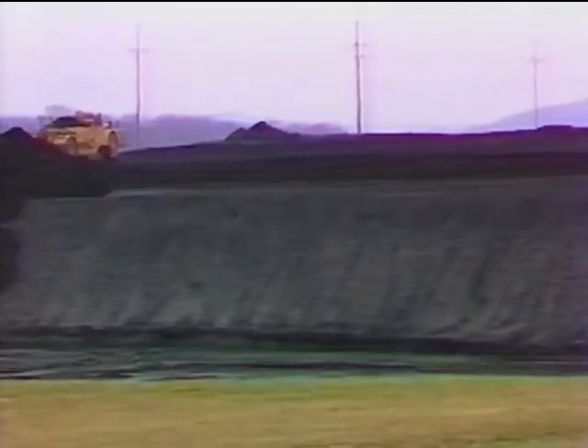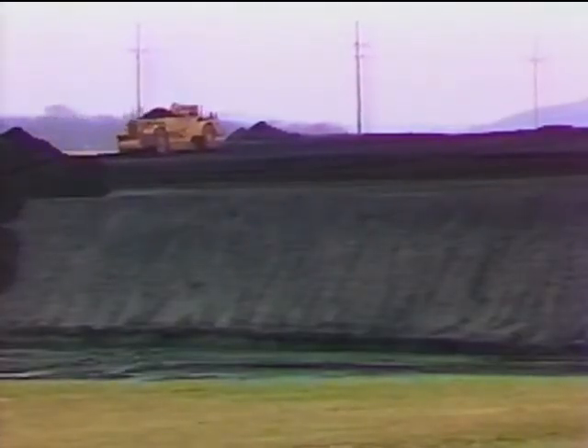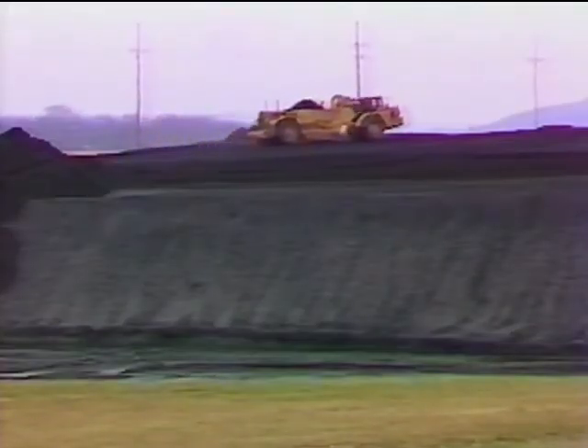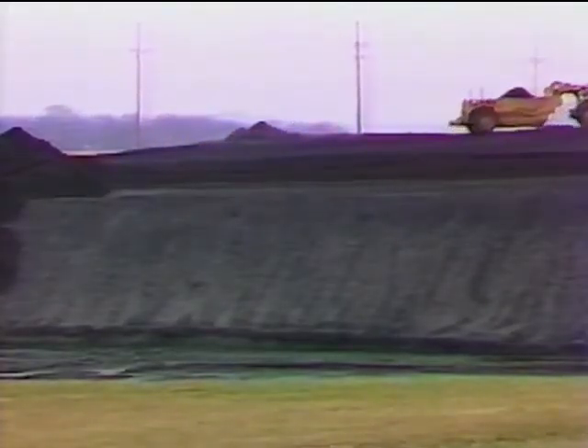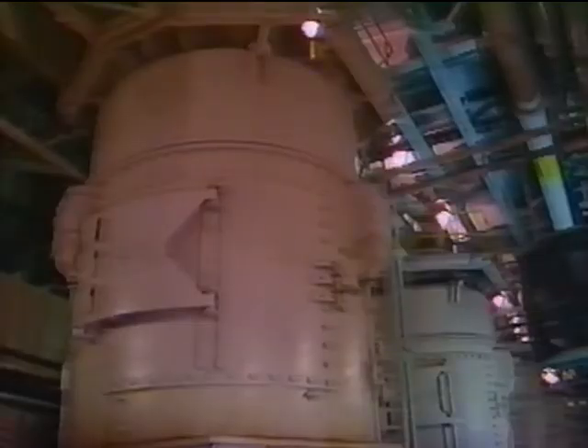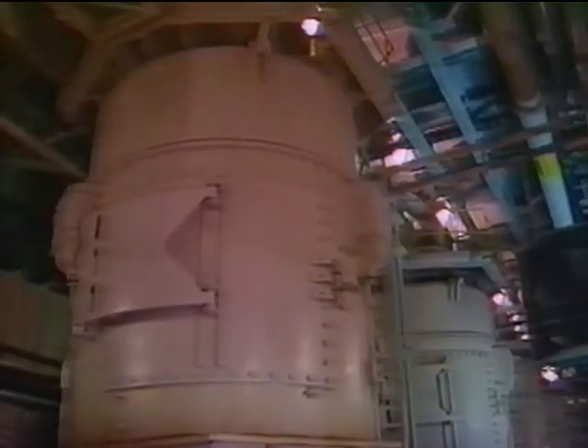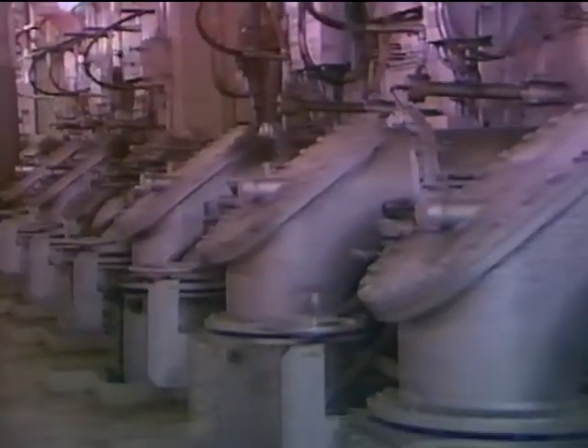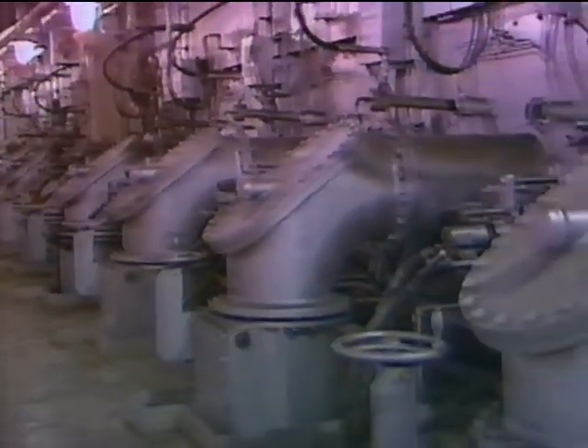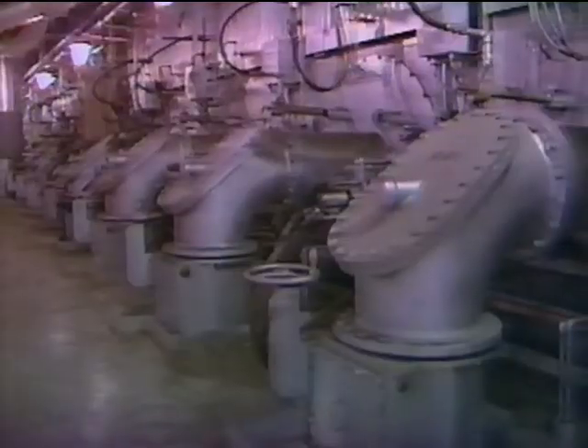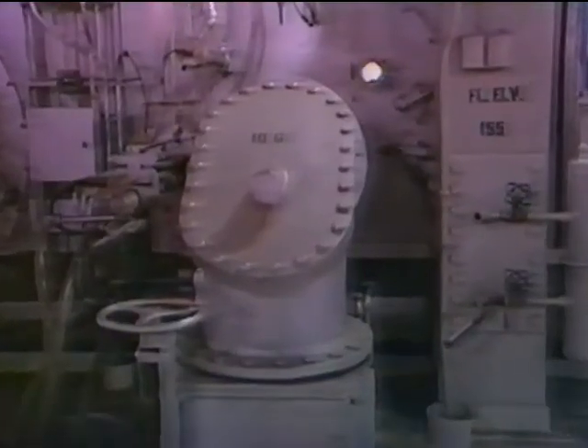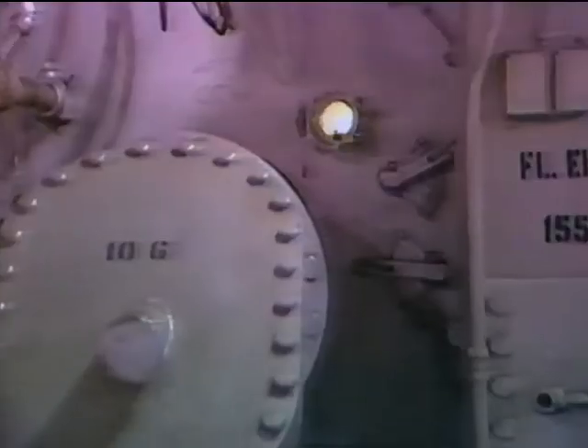The reclaim pile is used to keep a 30 to 90-day supply of coal, just in case there's a malfunction of the coal barge unloader, or in case barge traffic cannot reach the station. The usual route takes coal to the station's coal silos, where it meets the pulverizers. Zimmer is fitted with 14 pulverizers, each capable of grinding up to 140,000 pounds of coal per hour. Normally, the station burns 530 tons of coal per hour at full load operation. The coal is crushed to a fine powder, much like the consistency of face powder.